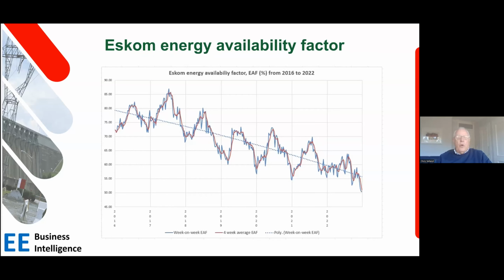The point I want to make is that the energy availability factor is the average of about 80 generators in the Eskom fleet. It's impossible to work on all 80 generators simultaneously - if you did, you'd have to shut down the whole country. So you have to maintain and fix these generators step by step, in sequence.